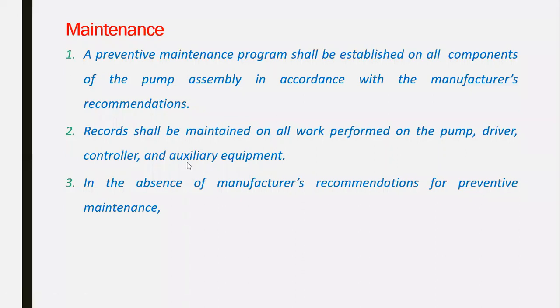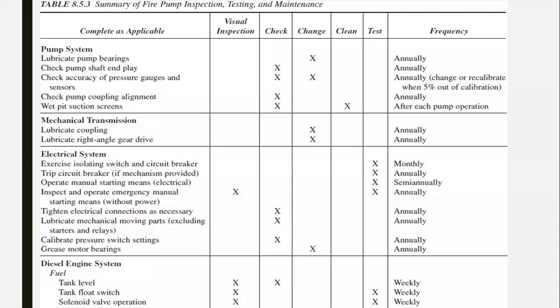All records should be maintained for all work performed on the pump, the drive, or the equipment. In the absence of the manufacturer recommendation for preventive maintenance, we can use these tables from the NFPA. This table from the NFPA, 8.5.3, is the summary for fire pump inspection, testing, and maintenance. It collects for you all of the visual tests and the checking and the changing or tests.